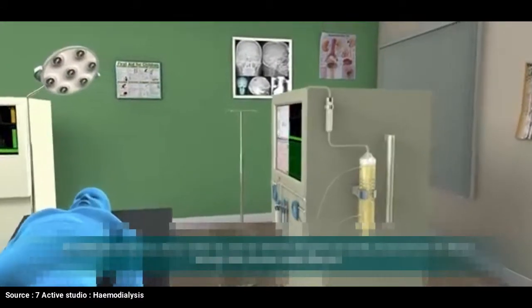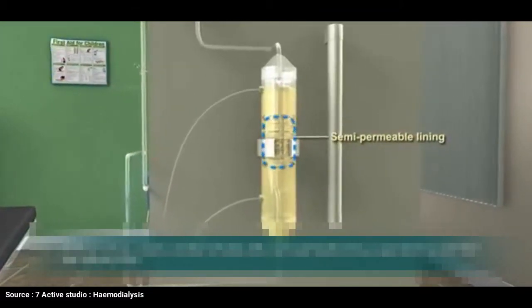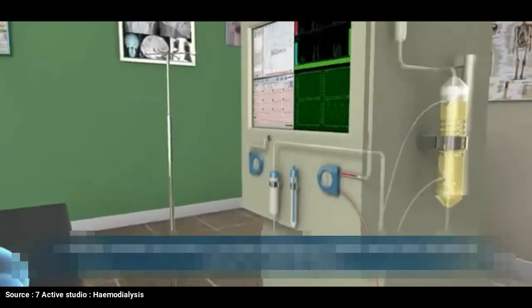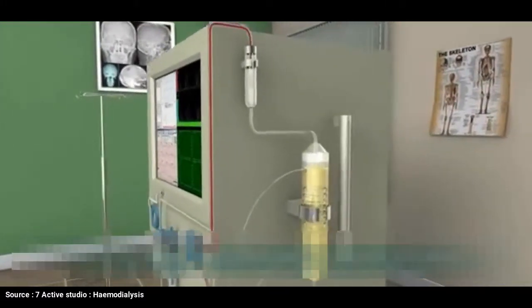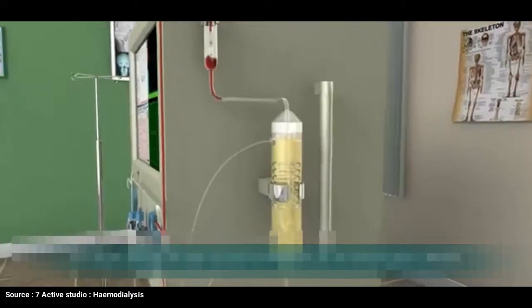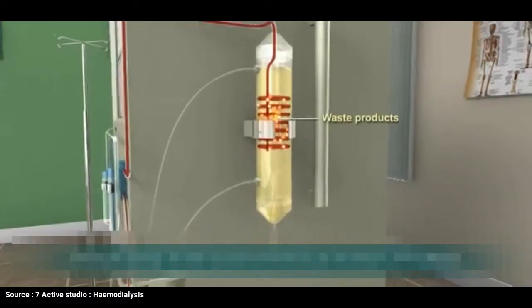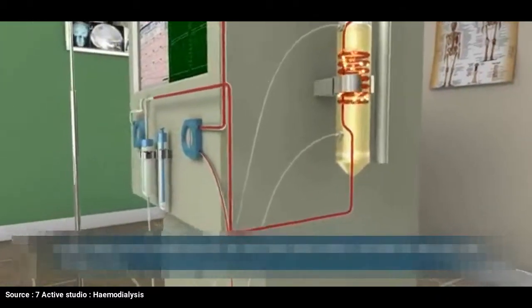Sterile filtration: Medical applications include guarding against microbial and particulate contamination of fluids being injected into a patient or used in haemodialysis. A typical dialyser module contains several thousand fibers in a 2-inch diameter tube, 1 to 2 feet long. Blood flows down the bore of the fiber, and an isotonic saline solution is circulated around the outside. Urea, creatinine, and other metabolites in the blood diffuse through the membrane to the dialysate solution. The process must be carried out slowly — typically 2 to 4 hours are required to eliminate all accumulated toxins.